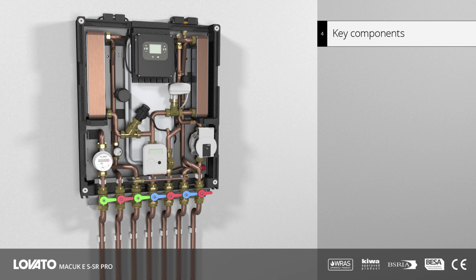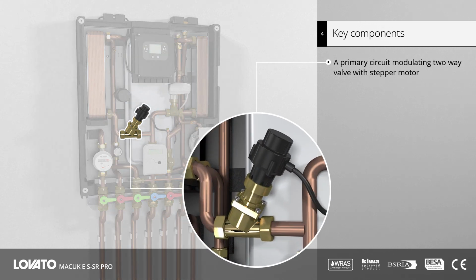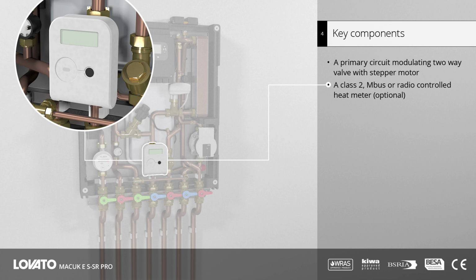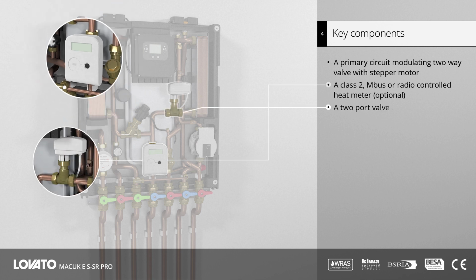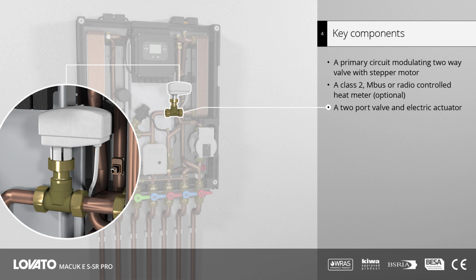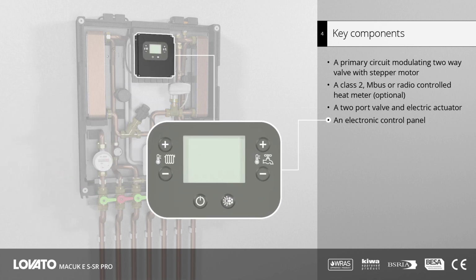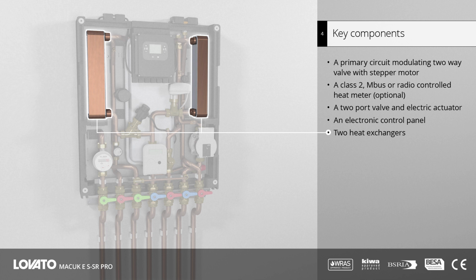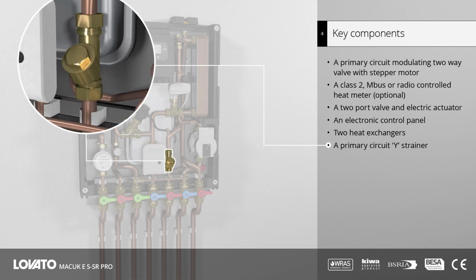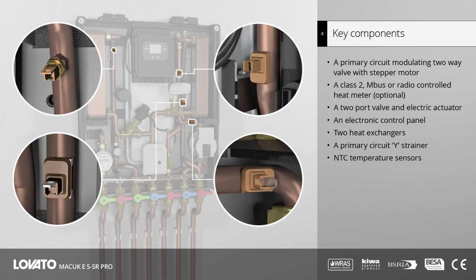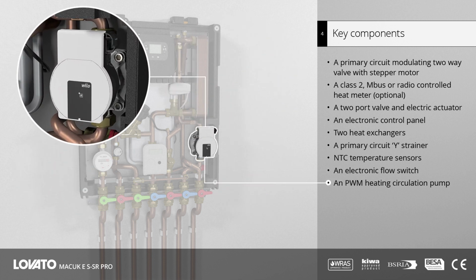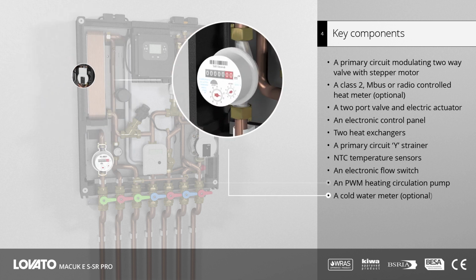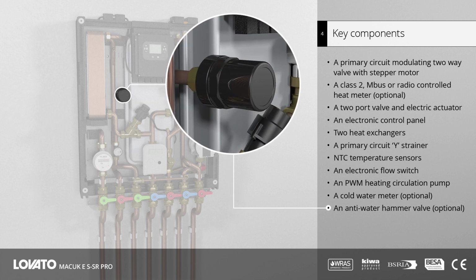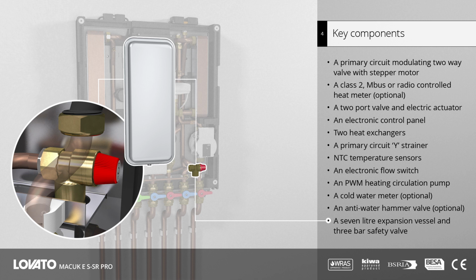Key components of the Macuk E include a primary circuit modulating two-way valve with stepper motor for the regulation of domestic hot water temperature, a Class 2 M-bus or radio-controlled heat meter for monitoring energy use, a 2-port valve and electric actuator for the regulation of heating and return temperature control, an electronic control panel, 2 heat exchangers, one for domestic hot water and one for heating, a primary circuit Y strainer, NTC temperature sensors on the primary flow, heating and domestic hot water circuits, an electronic flow switch, a secondary heating circuit PWM circulation pump, a cold water meter, an anti-water hammer valve, a 7-litre expansion vessel and 3-bar safety valve.